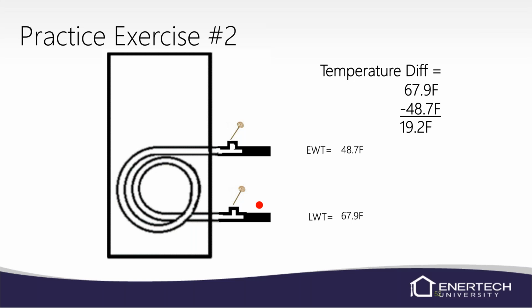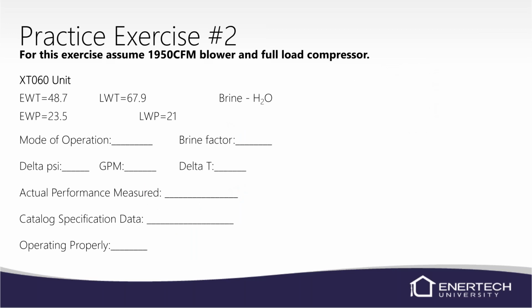Again, since we've got 48 degrees in and 67 out, the temperature coming in is lower than leaving, so we're rejecting heat. We're pulling heat from the home, putting it into the water, and rejecting it out to the loop field. Our entering water is less than our leaving water temperature. So our brine factor, I didn't tell you that before because I wanted to show you that 19.2, but again, our brine factor is water, H2O. So we're in cooling mode, we discussed that. The brine factor for straight water is 500.